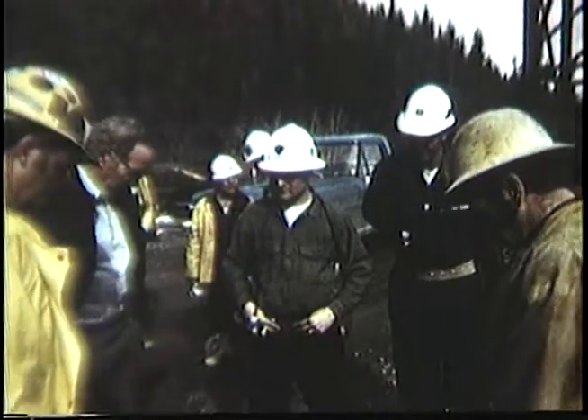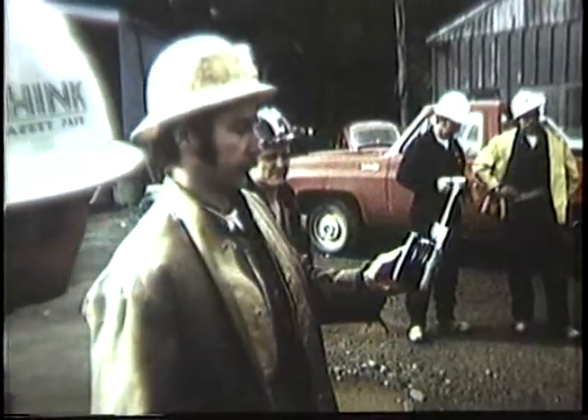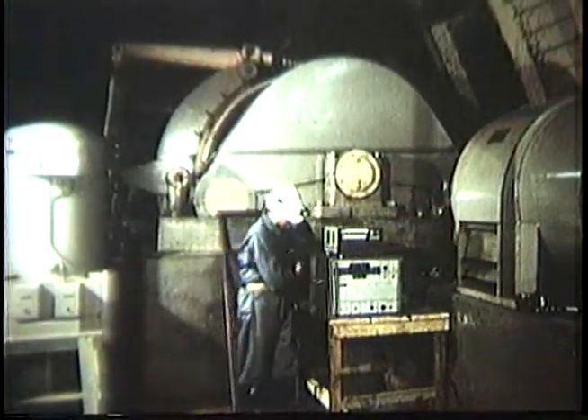The surface control unit was placed in the hoist room 3,000 feet above the level at which the controlled test fire was to be built. A test fire was ignited first at the mine portal to familiarize safety and mine personnel with the type of fire to be built and to demonstrate the steel pan in which the underground fire was built and controlled. Wood cribs built to underwriters lab specifications assured consistent fire conditions and test results. As a mine rescue team stood by to assist test personnel in the event of trouble, sensor response was evaluated and control of ventilation barriers, sprinklers, and all monitoring functions was conducted remotely from the surface control unit in the hoist room 3,000 feet up the shaft.